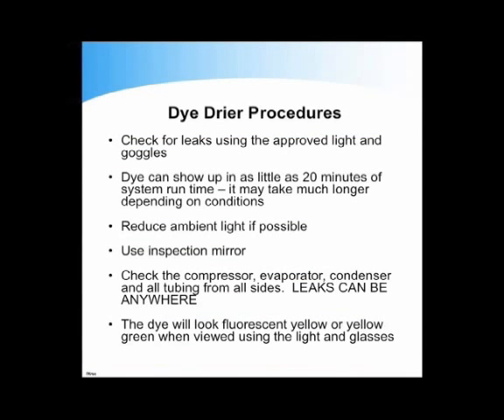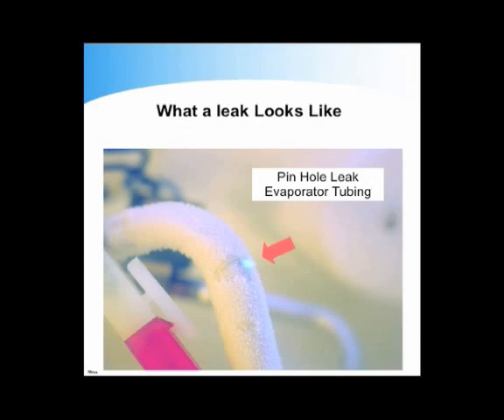Dye dryer procedures. Check for leaks using the approved light and goggles. Dye can show up in as little as 20 minutes of system runtime. It may take much longer depending on conditions. Reduce ambient light if possible. Use an inspection mirror. Check the compressor, evaporator, and condenser, and all tubing from all sides. Leaks can be anywhere. The dye will look fluorescent yellow or yellow-green when viewed using the light and glasses.